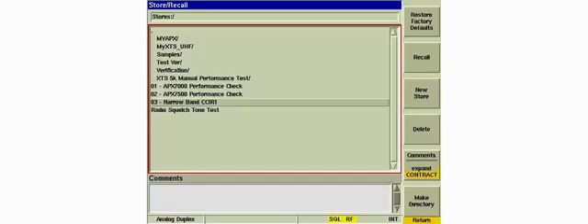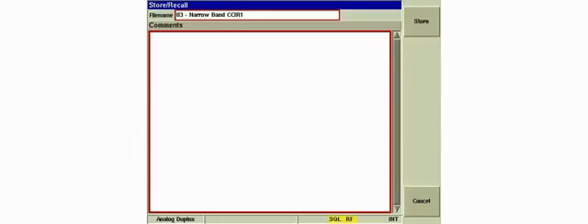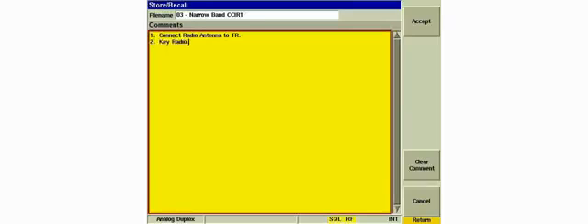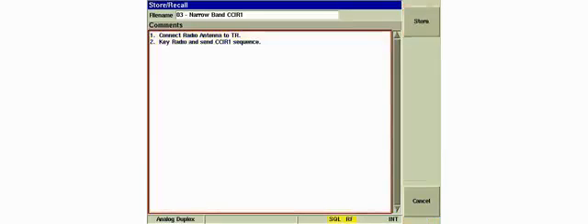We've already recalled the Narrowband CCIR1 settings, so overwriting the settings will not erase anything important. Selecting the setting, then pressing the New Store soft key will overwrite the stored settings. Before storing, select the Comments field to enter any statements concerning the setup. When finished entering comments, press the Accept soft key. Press the Store soft key.